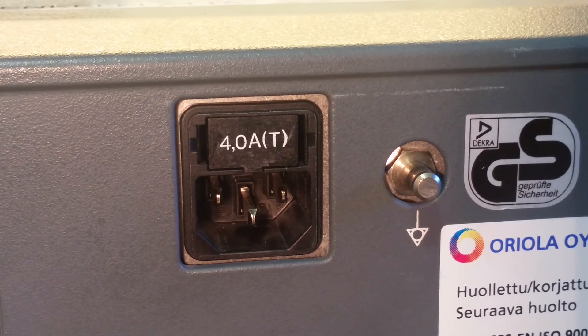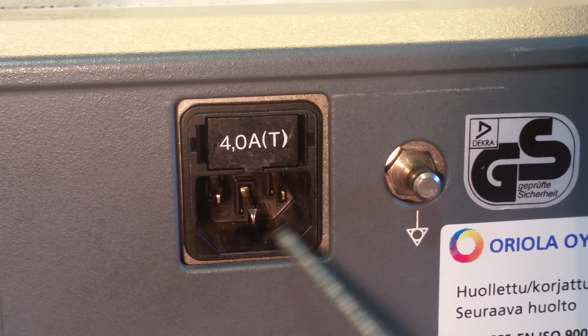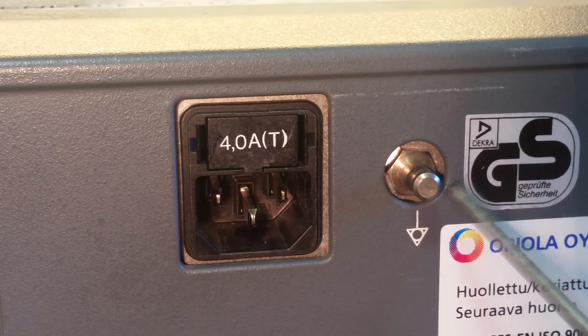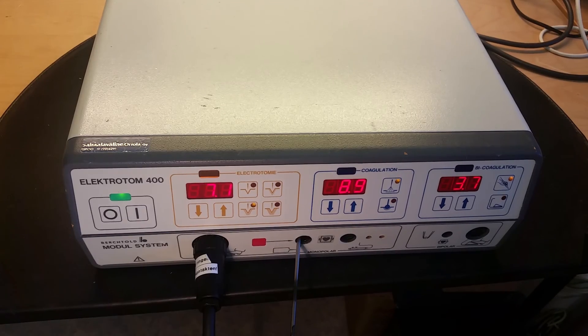Just for if you are interested: it has a 4 amp slow fuse, and there's the earth tap. All medical equipment has this earth tap on them. So there you have it - the Elektrotom 400. Thanks for watching.